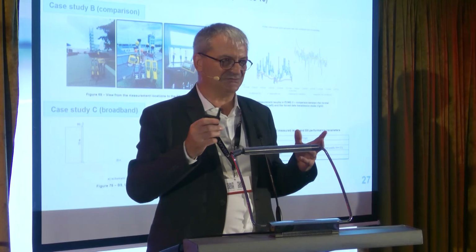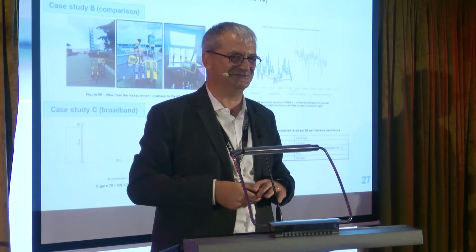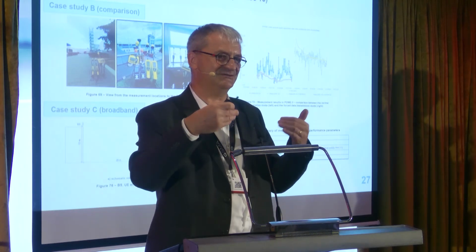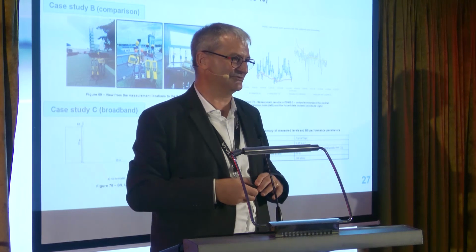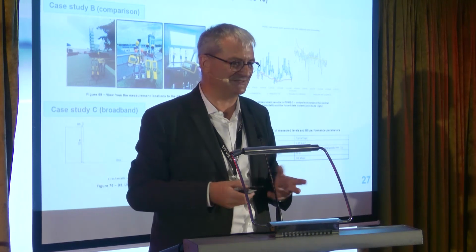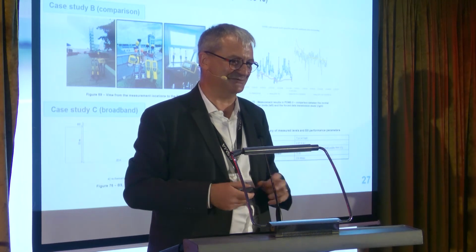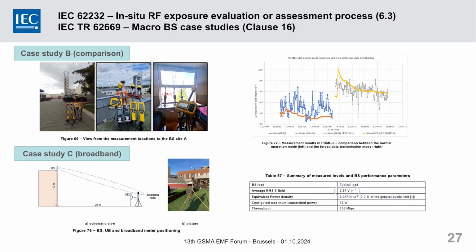We had a bit of discussion in the committee because the probes are very close to each other, which is not the usual way to do it. But the error was taken into the calculation of the comparison, so the standard implementation is correct. Even if normally we only put one probe when doing such measurements. And below, it's another case study, so you will see the equipment behind.